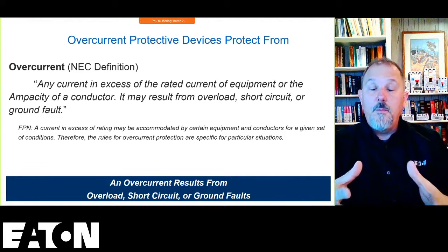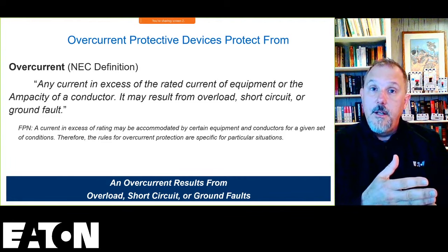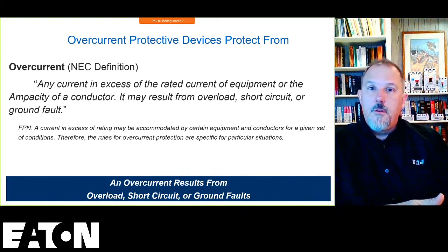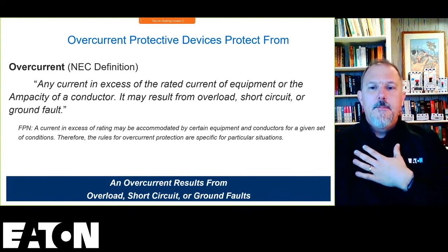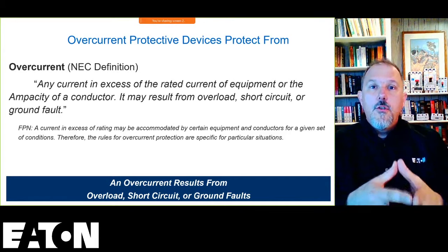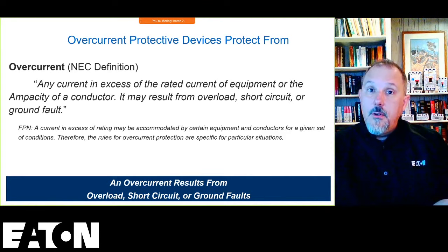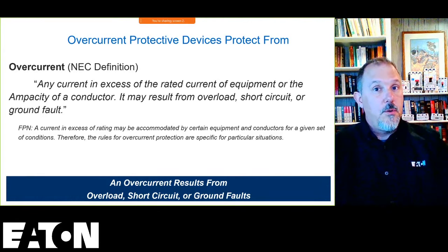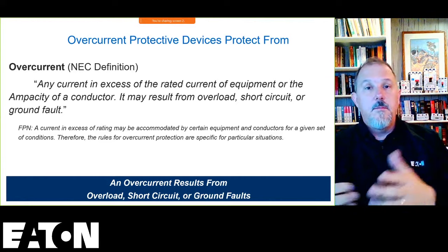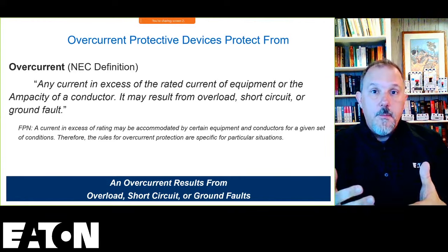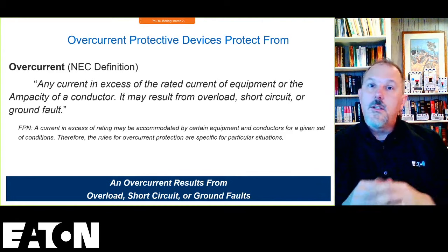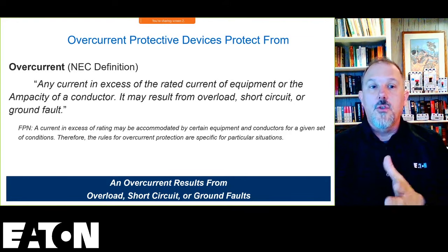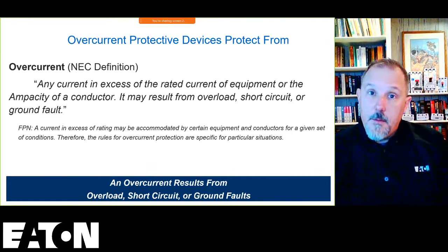Now, not all of those could be providing the protection for a conductor. You may have the short circuit protection from, say, the circuit breaker or fuse, and you may have the overload protection done by, say, an overload heater element, or it may be a part of the air conditioning unit, so to speak, the controller and whatnot that's managing the starting of the motors and all this other good stuff that's in the AC unit. The overload protection in many, if not most cases, is closer to the motor. So your breaker or your fuse is just providing short circuit protection and ground fault protection.